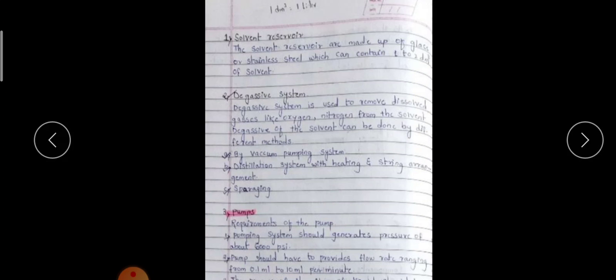Going one by one — the solvent reservoir: its function is to store the solvent. It is made of glass or stainless steel and can contain one to two liters of solvent. The degassing system is used to remove dissolved gases like oxygen and nitrogen from the solvent. Degassing can be done by vacuum pumping, by distillation with heating and stirring, or by sparging.